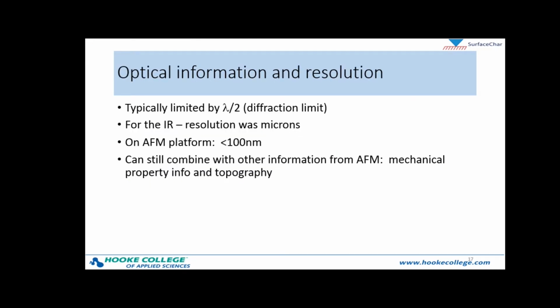Now, before we go into some of the AFM-IR examples, I just wanted to say a few words about resolution and this optical information. Typically, optical spectroscopy measurements such as Raman and IR are limited by the diffraction limit, which is lambda over 2, where lambda is the wavelength of the incident light. For the IR, which typically has very long wavelengths associated with it, that meant the resolution was limited to microns. So to be able to put this onto an AFM platform and achieve resolution of less than 100 nanometers very easily, and in some cases even less than 20 nanometers, is very impressive.